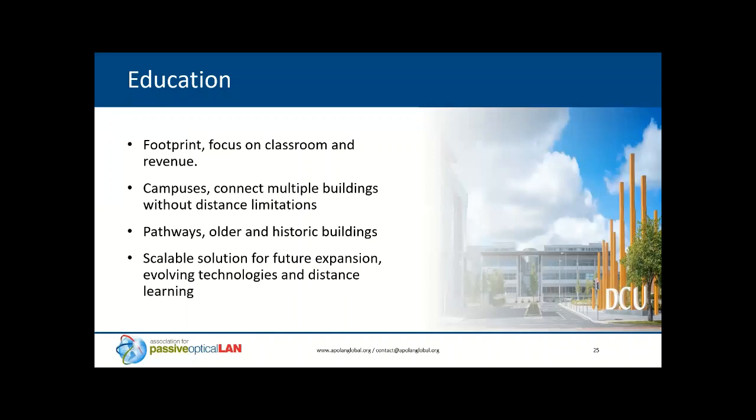A lot of the education uses zone distribution. Some of them kind of prefer it. In some cases, they just have a wing of classrooms where they don't have a closet, so they're putting in just a zone box, putting an optical splitter in there, maybe a remote power PDU, and they're feeding all of these classrooms and devices in these individual wings. They're not needing an IT closet everywhere they start building out. We're able to reduce that footprint.